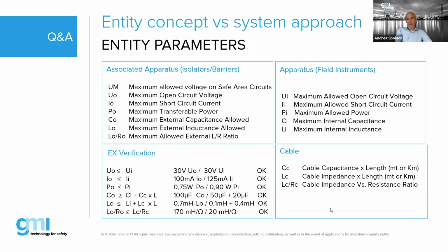So, sorry Andrea, it sounds very complex. I just want to mention that there are two concepts: the system concept, where everything is certified as a block, and the entity concept, where each device is certified individually and you must put them together by verifying the safety parameters. This sounds complicated, and one might ask, why not just do the system approach? The system approach limits you—once you've certified a system with that specific transmitter, barrier, or device, you cannot make any change to it. Whereas with the entity parameter approach, as long as the parameters match, you can use any supplier or manufacturer.